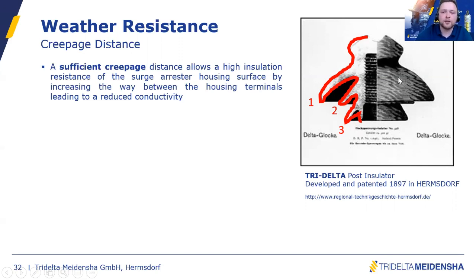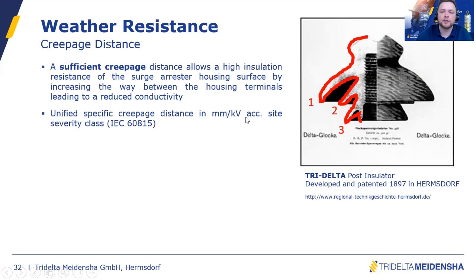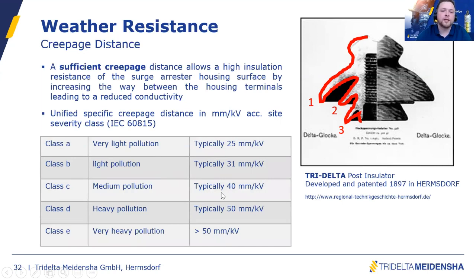So we are talking about creepage distance, which gives us pollution performance. And when we want to select a surge arrestor with a specific pollution performance, we have to standardize this, and this is done in the IEC 60815, which gives the unified specific creepage distance in millimeter per kV. So the bigger the rated voltage of the surge arrestor, the bigger the creepage distance has to be, and this is classified. We have class A to E, and very light pollution for areas where typically it doesn't play a role, there's only rain. So normally we use a specific creepage distance of 25 millimeter per kV. And then we have light pollution, medium, heavy, and very heavy. And the specific creepage distance is rising according to this pollution area.